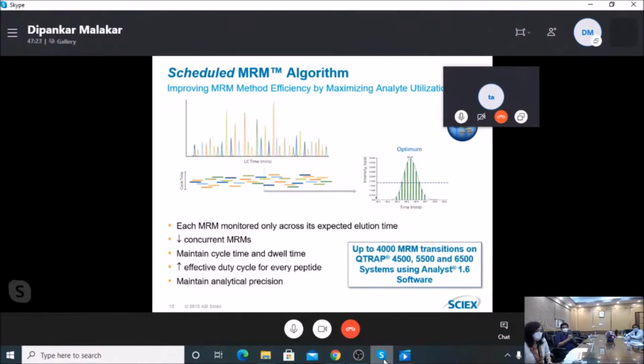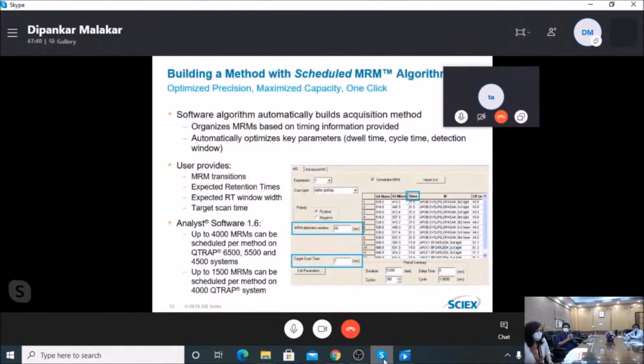And it supports Analyst software, version 1.6. It supports this higher number of MRM transitions, like more than 4,000 MRM transitions - now it is possible to run through a single run. So building the method, as I said, there is a timing component, and the software algorithm automatically builds the acquisition method, organizes MRM based on timing information, automatically optimizes key parameters - dwell time, cycle time, and detection window - and MRM expected retention time, with target scan time. The user needs to provide this in the Analyst software, and up to 4,000 transitions can be monitored here.